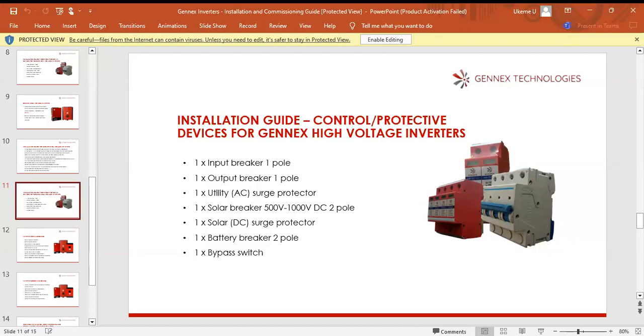Then one utility AC surge protector, then a solar breaker, which is high voltage from 500 volts to 1000 volts. A DC 2-pole breaker is recommended. One solar DC surge protector, depending on the number of inverters and the solar inputs you have. One battery breaker, which is double pole because you need high current, so 250 amps thereabouts. You need to loop the breakers together. And a bypass switch to allow your customer to bypass the inverter if there is any issue or during troubleshooting, so the person can go back to direct supply.